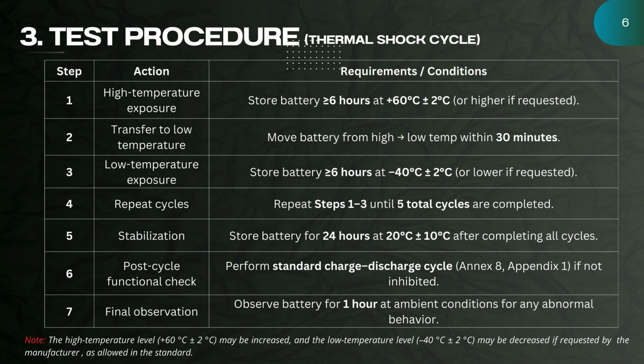Step 4. These steps are repeated until 5 complete cycles are achieved. Step 5. After completing the cycles, the battery is stabilized for 24 hours at 20 degrees Celsius plus or minus 10 degrees Celsius. Step 6. A standard charge-discharge cycle is performed as per Annex 8, Appendix 1, if not inhibited by the device. Step 7. Finally, the battery is observed for 1 hour for any abnormal behavior. The note below highlights that higher high temperature levels or lower low temperature levels may be used upon manufacturer request.